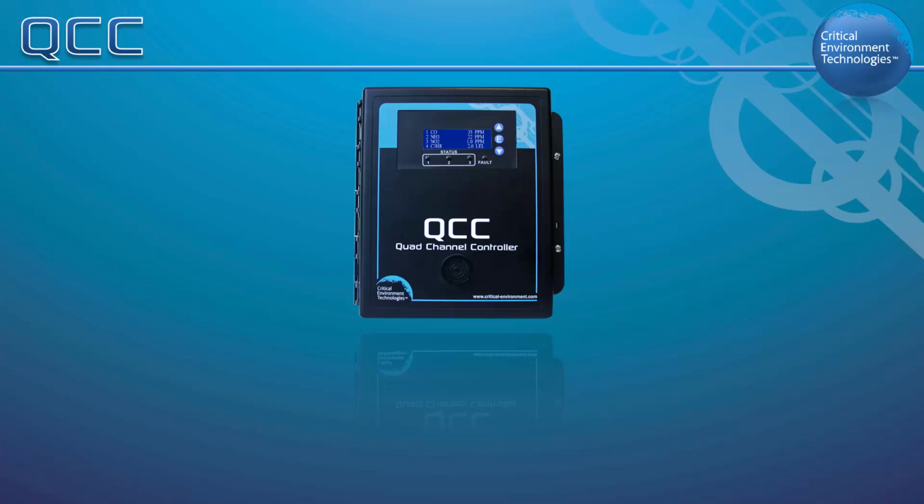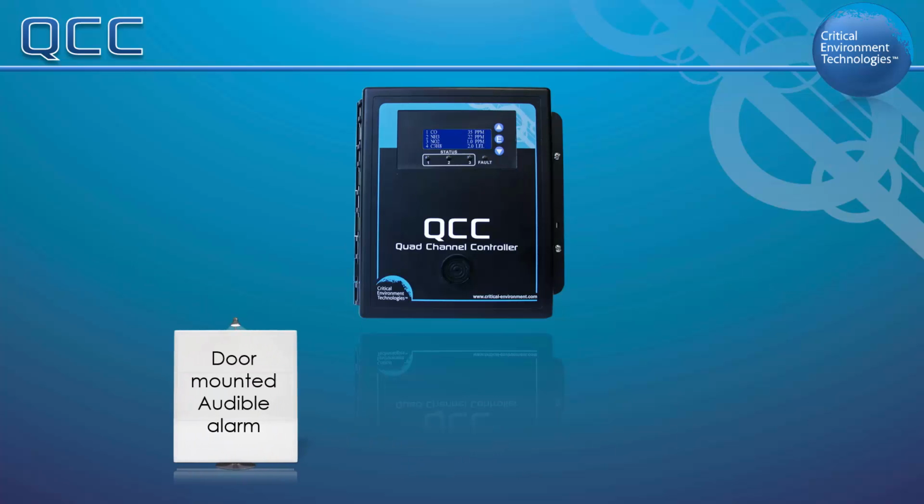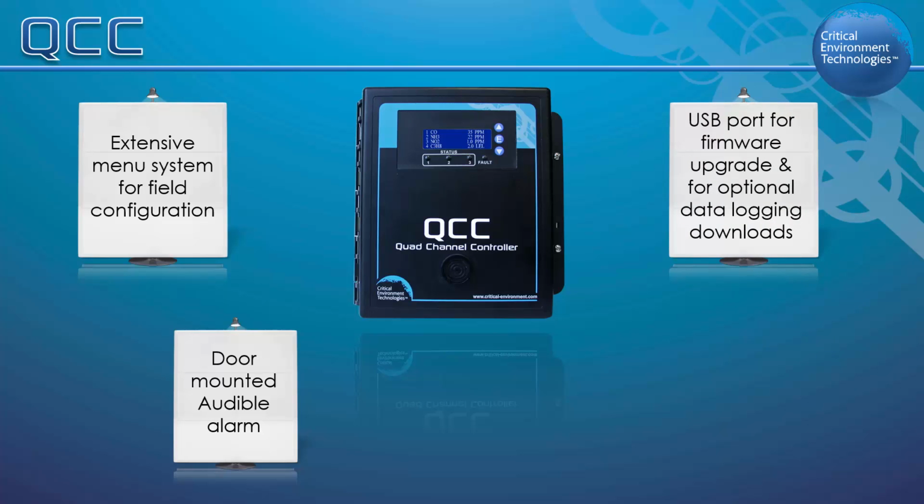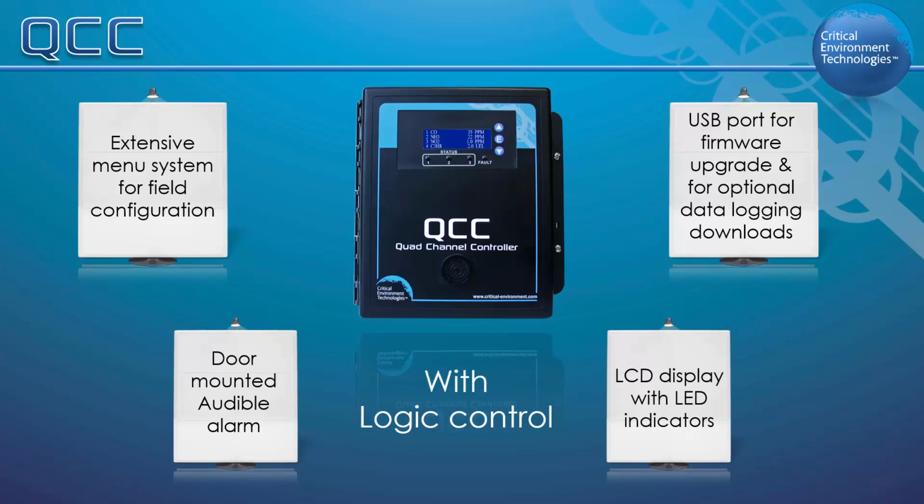It has a door-mounted audible alarm, an extensive menu system with several levels of password protection that allows for customizable configurations in the field to meet specific application requirements, a USB port for firmware upgrades, and if the optional analog output option is installed, the USB port can also be used for data logging. It has logic control and an LCD display with LED indicators for channel alarm status and fault conditions to provide you with the necessary monitoring information.